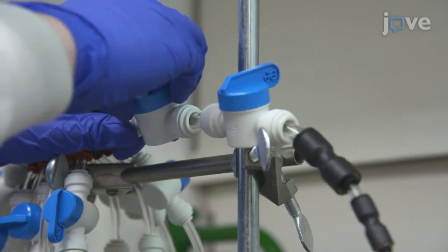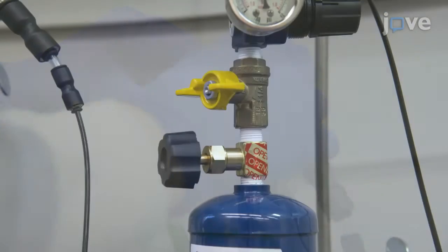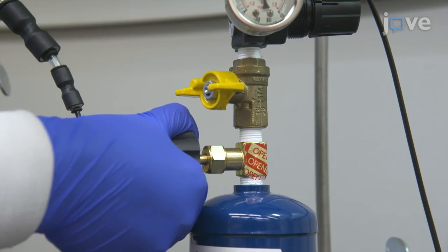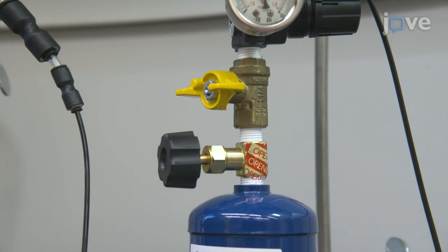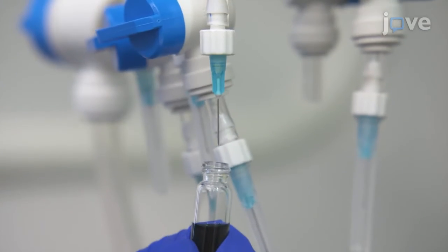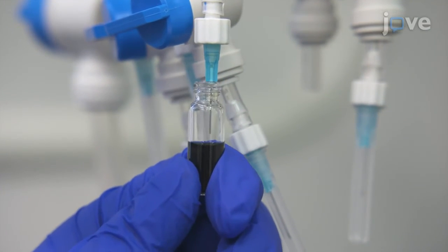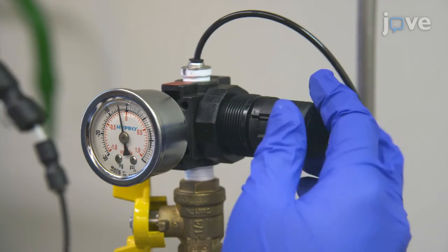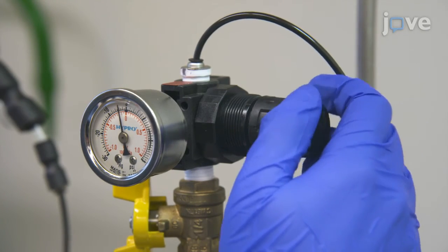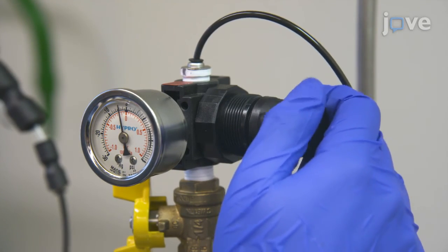Open pressure valve A and pressure valve B, and turn the gas cylinder valve approximately 1/16 to 1/8 counterclockwise to partially open it. Open the T-handle valve and uncap the sample vial with the lipid solution. Place the manifold needle above the vial's liquid-air interface.